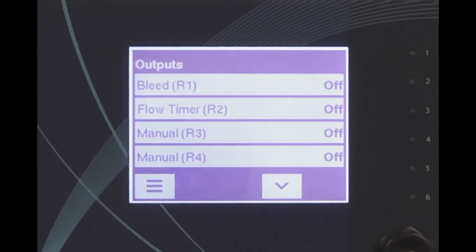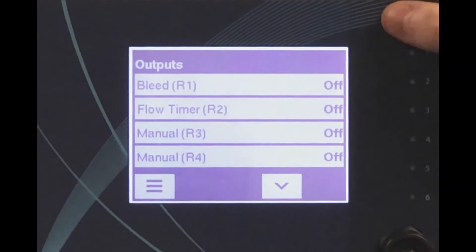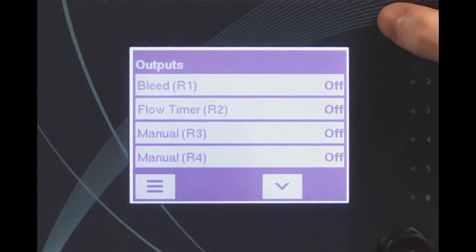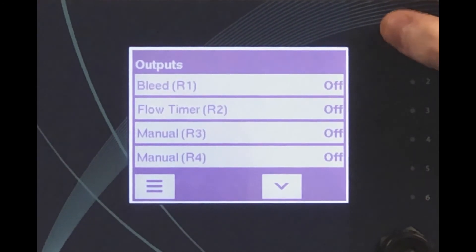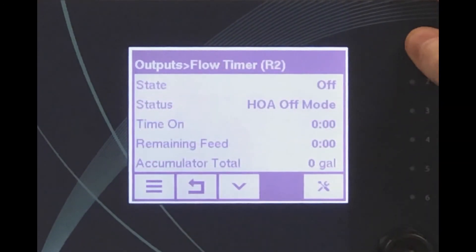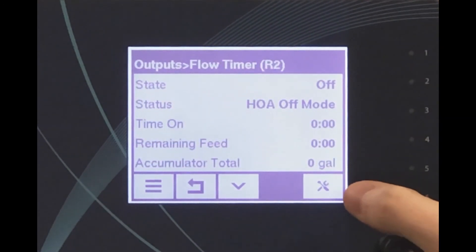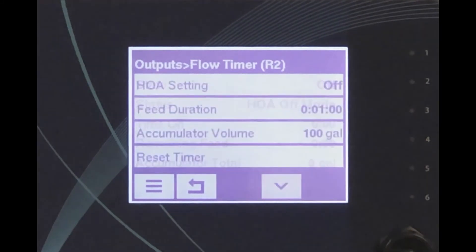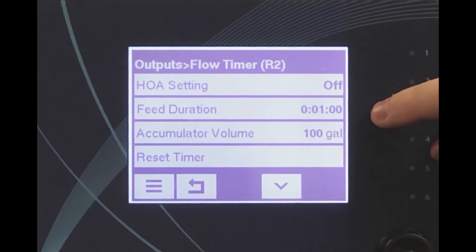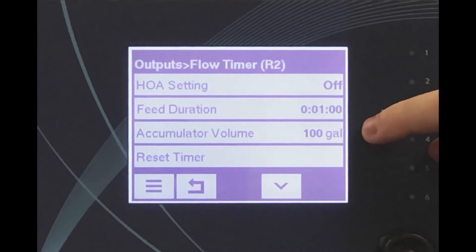Chemical feed algorithms for boilers are similar to those used for cooling towers. The most common feed algorithm used for boiler chemical feed is a flow-based timer feed. The water meter measures the water as it is added to the deaerator or feed tank and turns a chemical pump on for the specified amount of time per accumulated volume.